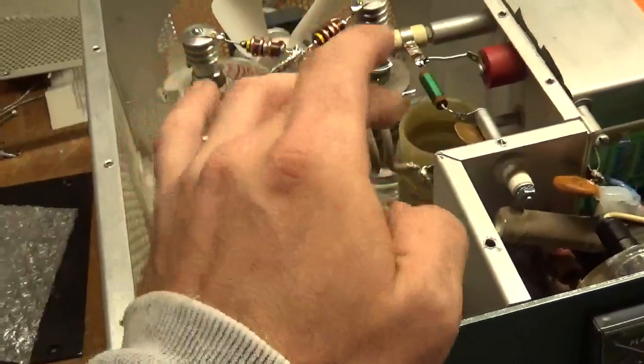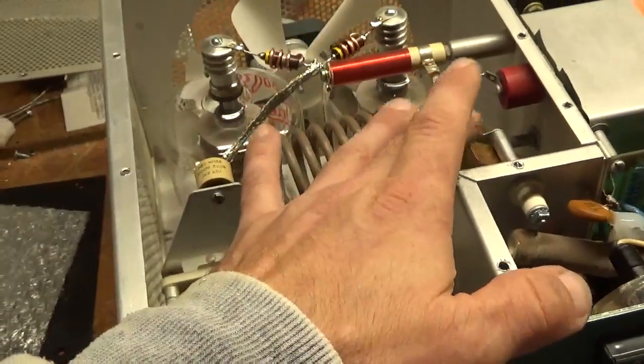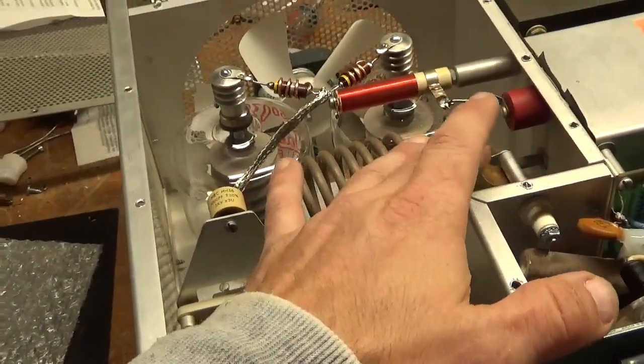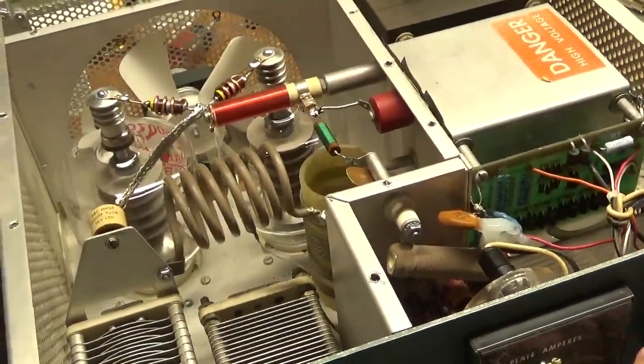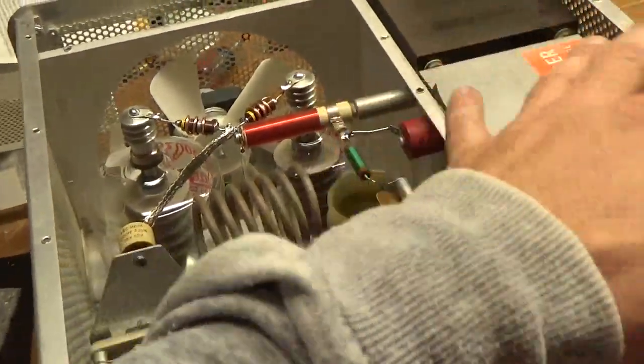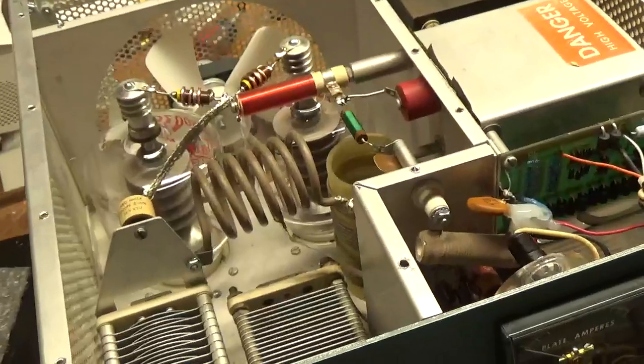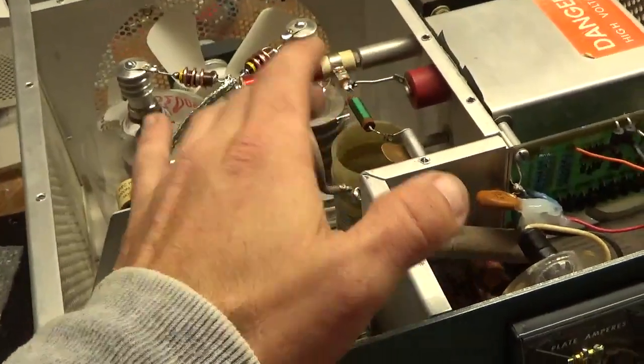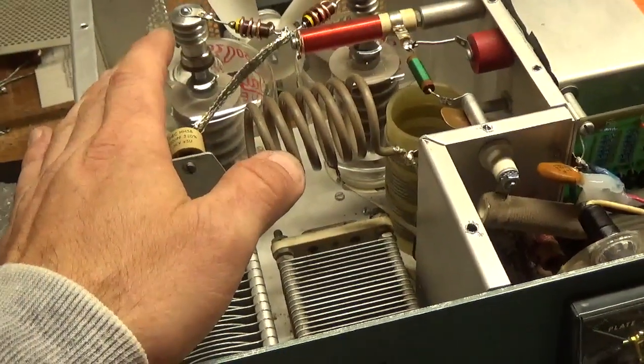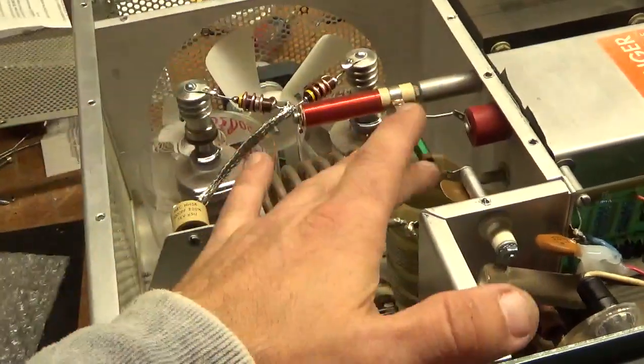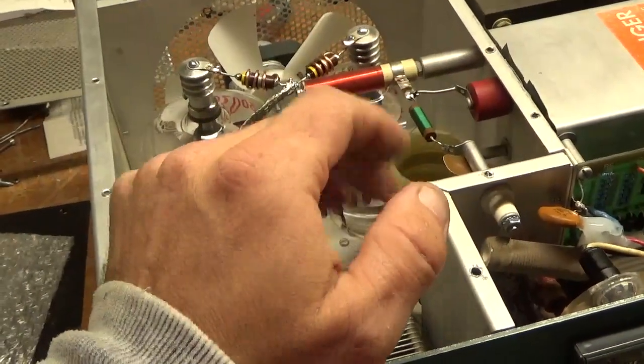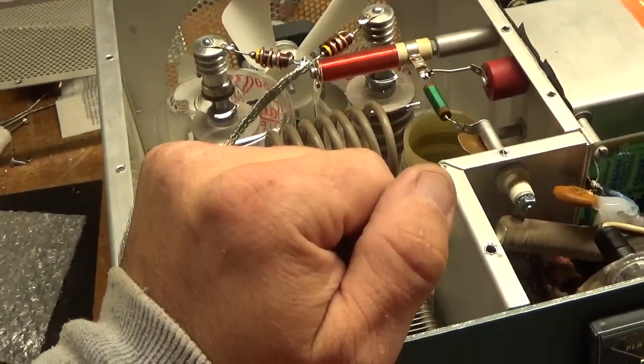Now that works good. Puts a crowbar, puts a short on the B positive. You know, the bleeder should bring it down, but in case the bleeder opened, you still had residual voltage charged in the filter caps. This will put a hard short on it, bringing it to ground. Or if you leave the cover off, it'll bring it to ground. Keep you from getting electrocuted one way or another.